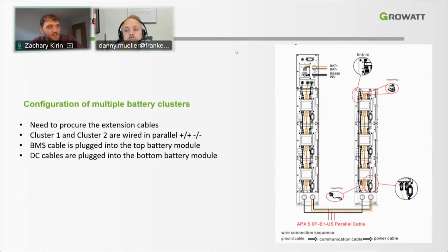So multiple battery clusters can be supported together. Again, this inverter can be floor to ceiling, or we can install two different battery modules, basically kind of separated with each other with one main power module. So you'll need to procure some extra extension cables as well as an extra floor base. And currently, right now, the battery positive and minus are working as normal. And then it would go out the bottom through these conduit holes and into the next bottom on the side.